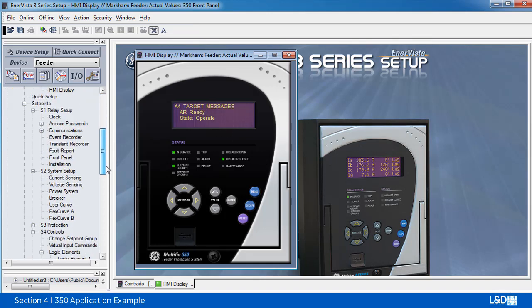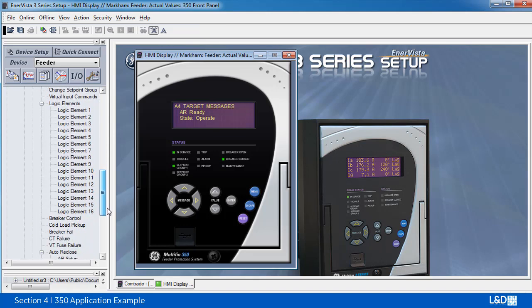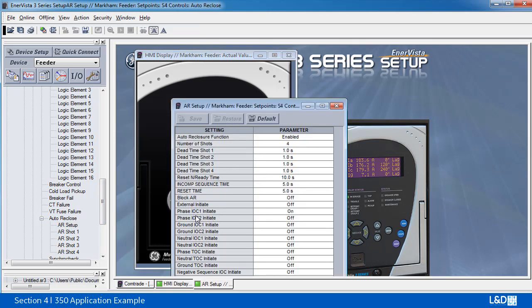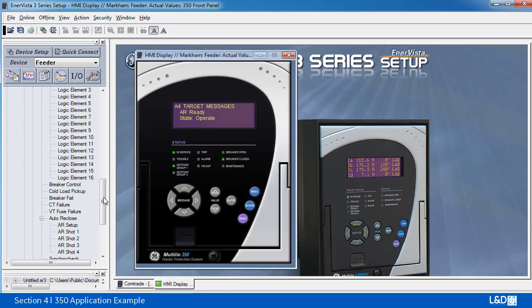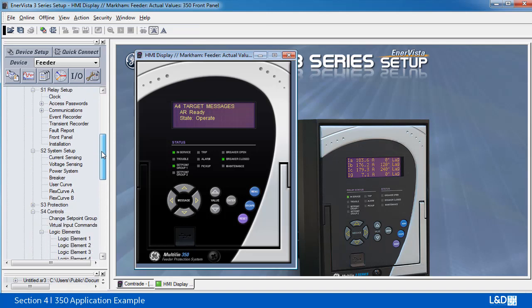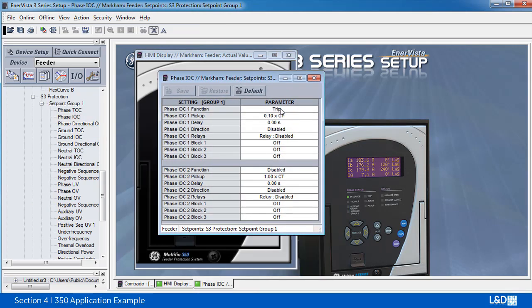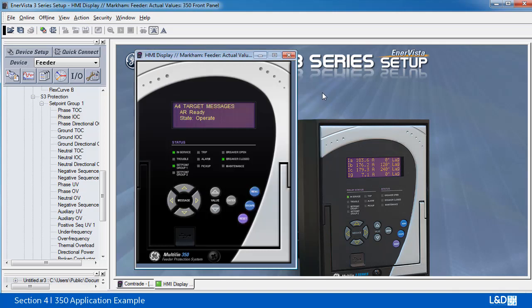By the way, I also need to inject the trigger for the auto-reclose. In the setting I used Phase IOC. Phase IOC initiate is set on, so I need to make sure my Phase IOC is enabled. Go to the protection, Phase IOC, and the function is set to trip. Pickup is 0.1 CT. So now I'm going to use the RTT test set to inject the current to trip the Phase IOC. Okay, so now I see the Phase IOC tripped.